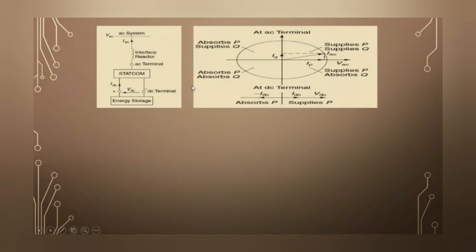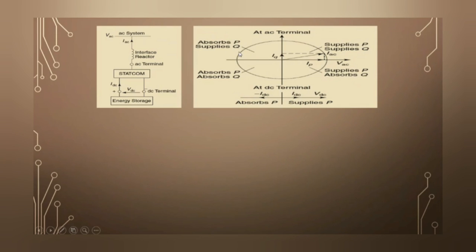This is the basic four-quadrant diagram. In the first quadrant, supply voltage and AC current are in phase, so it supplies both reactive and active power. In the second quadrant, it supplies reactive power but absorbs active power. In the third quadrant, it absorbs both reactive and real power. In the fourth quadrant, it absorbs reactive power and supplies active power.